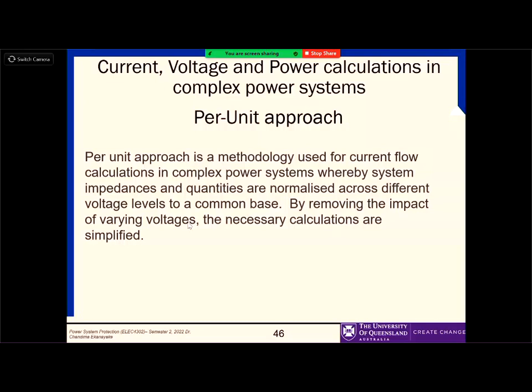It's easier for software to work it out, because when doing calculations in different voltage and current levels, the error in one level could differ from another, since you're working with magnitudes. Say in the lower voltage level, if it's 1000 amps, you can have plus or minus 10 amps, giving 1010 or 990, which is fine. But when you move to another level where that same 1000 amps reflects as 50 amps, and you set the same scale, 50 plus 10 is 60, minus 10 is 40. Now 40 to 60 is meaningless, the error is too large. That's why it's better to work in the same scale.